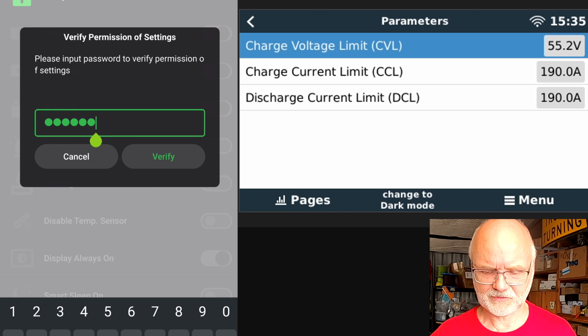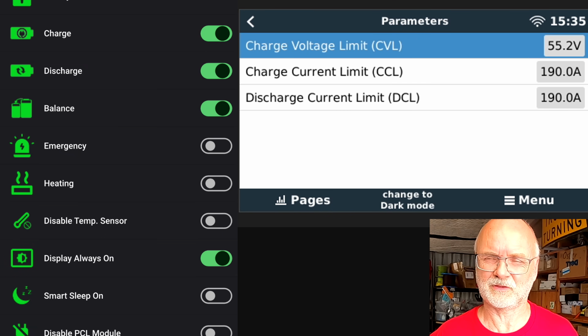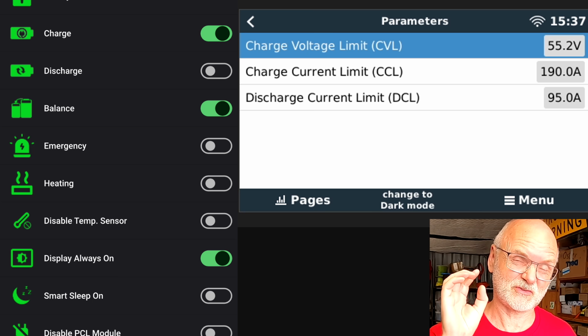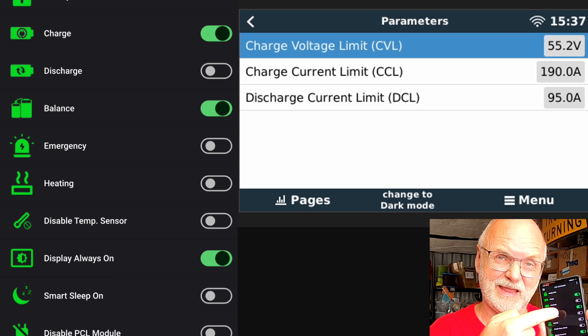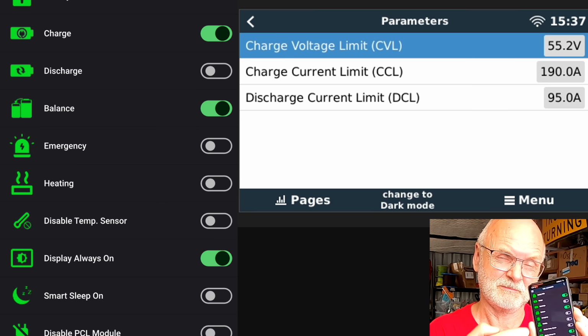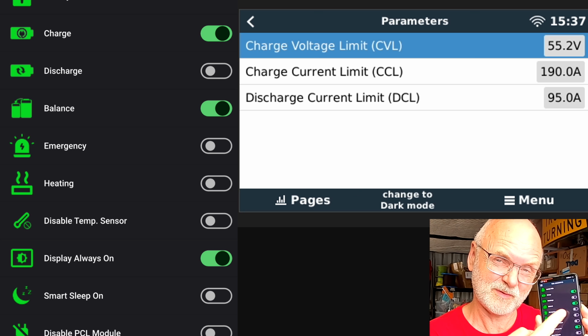Perfect. Okay, so what happens if one of your cells hits an under voltage protection and the BMS turns off this one battery? So we turn off our slave battery here, discharge off, because one cell is low, it goes back to 95. And in this case, it would only keep discharging the master battery because the slave has got an under voltage protection and the BMS has turned off the MOSFET.